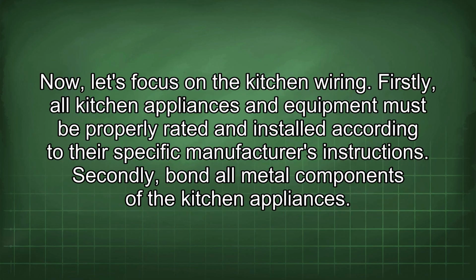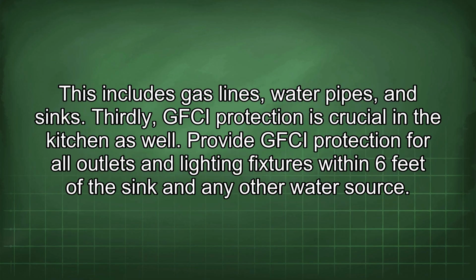Now let's focus on the kitchen wiring. Firstly, all kitchen appliances and equipment must be properly rated and installed according to the specific manufacturer's instructions. Secondly, bond all metal components of the kitchen appliances. This includes gas lines, water pipes, and sinks. Thirdly, GFCI protection is crucial in the kitchen as well. Provide GFCI protection for all outlets and lighting fixtures within 6 feet of the sink and any other water source.